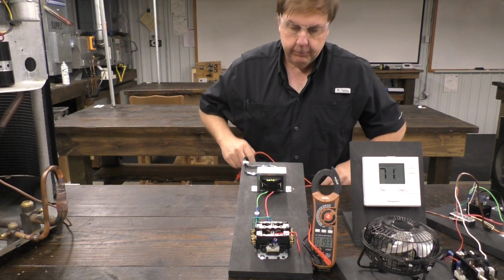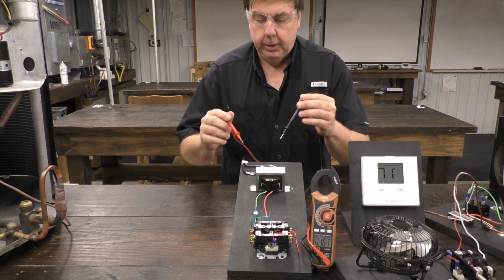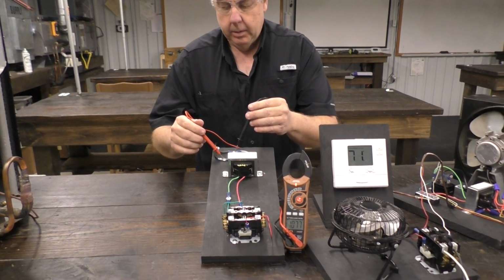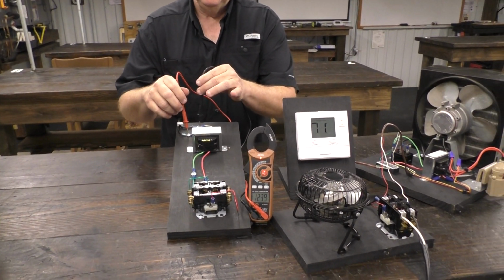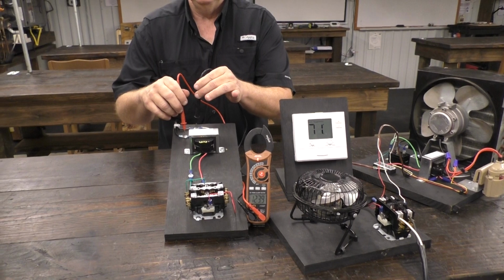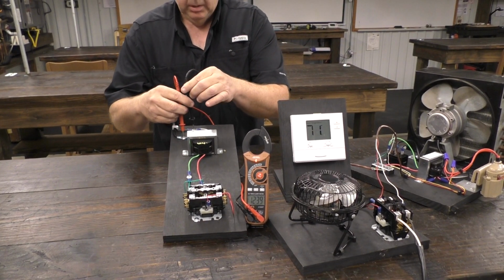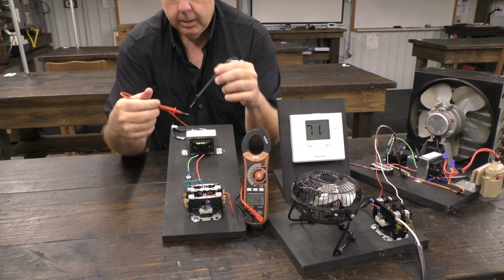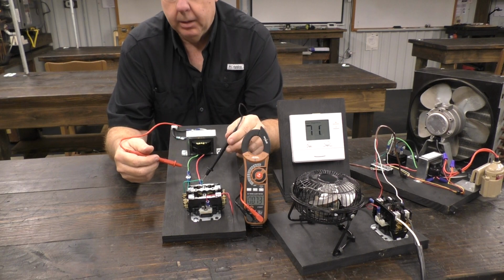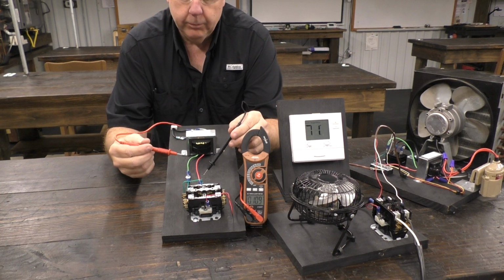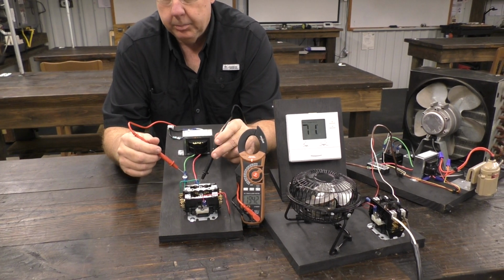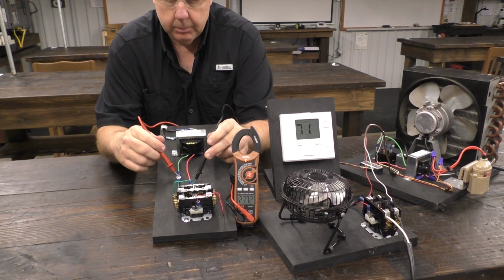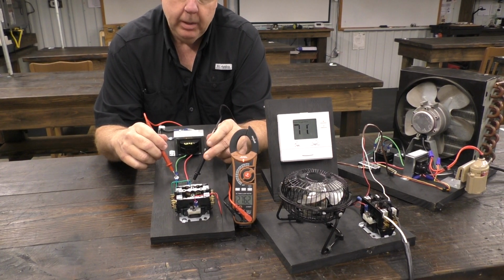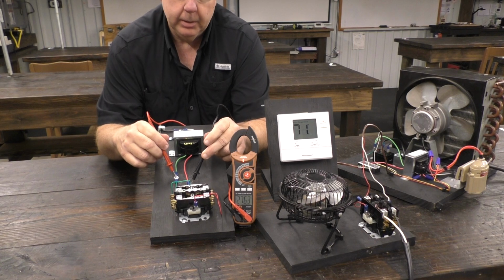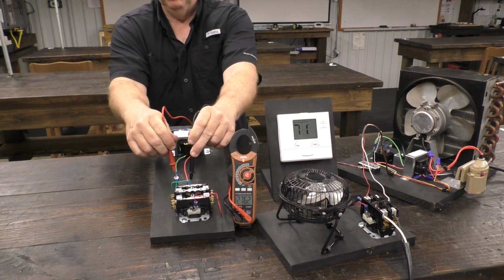What we're going to read is the voltage going into the transformer, up here on top. If I read it here, we should see at least over 100, say 120 volts or so. If I read the secondary side of the transformer, that's our control voltage. That's going to be a lower voltage, most likely 26 or 27 volts on the meter. That's what's pulling in our contactors.